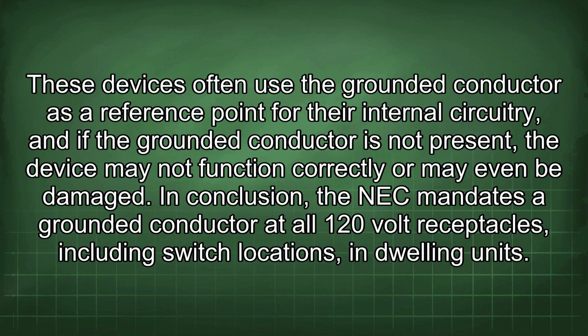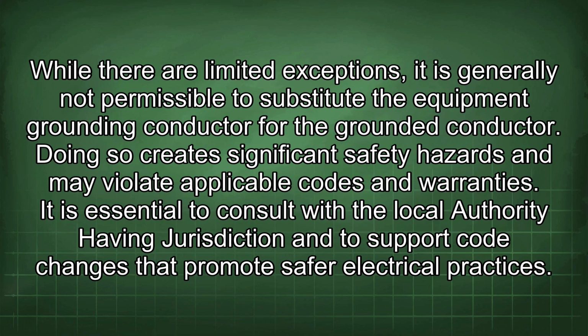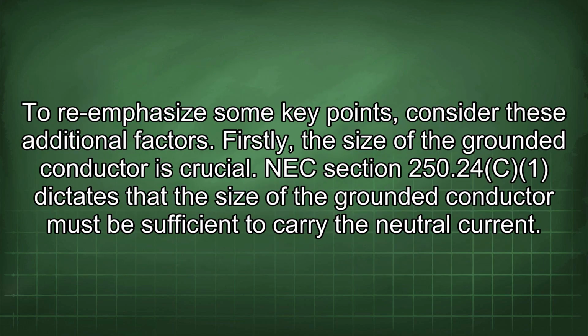In conclusion, the NEC mandates the grounded conductor at all 120-volt receptacles, including switch locations, in dwelling units. While there are limited exceptions, it is generally not permissible to substitute the equipment grounding conductor for the grounded conductor. Doing so creates significant safety hazards and may violate applicable codes and warranties. It is essential to consult with the local authority having jurisdiction and to support code changes that promote safer electrical practices. To re-emphasize some key points, consider these additional factors.